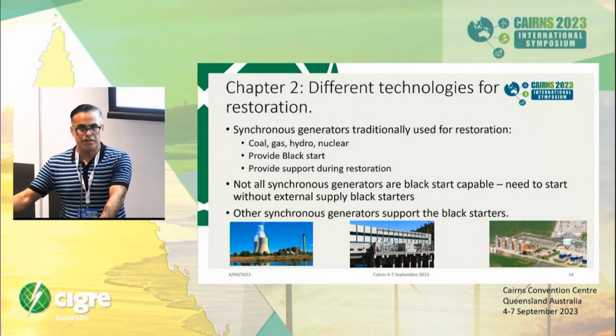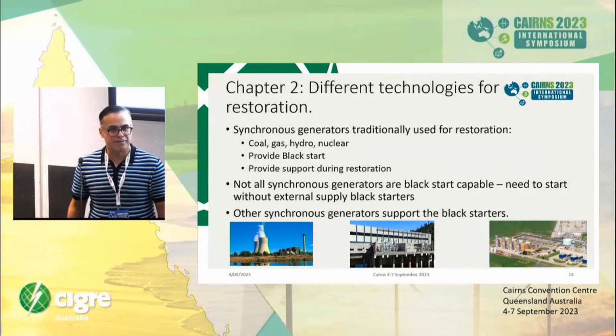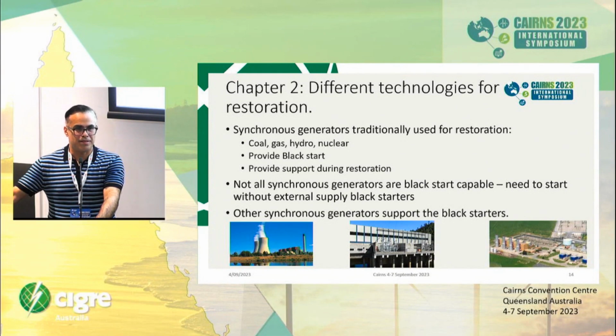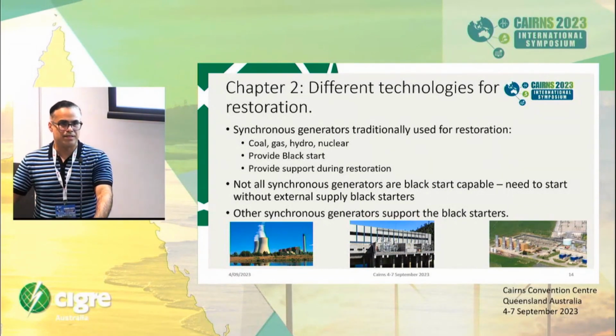That's not why I mentioned. I think the response, because my voice is not coming up. So I think the question was whether there have been demonstrated experiences. The restoration plan is always for a network, not for a generator. That's why I mentioned that testing of individual components has been done for several decades. We didn't want to waste our time, basically. So transformer energization and all this consideration is part of it.